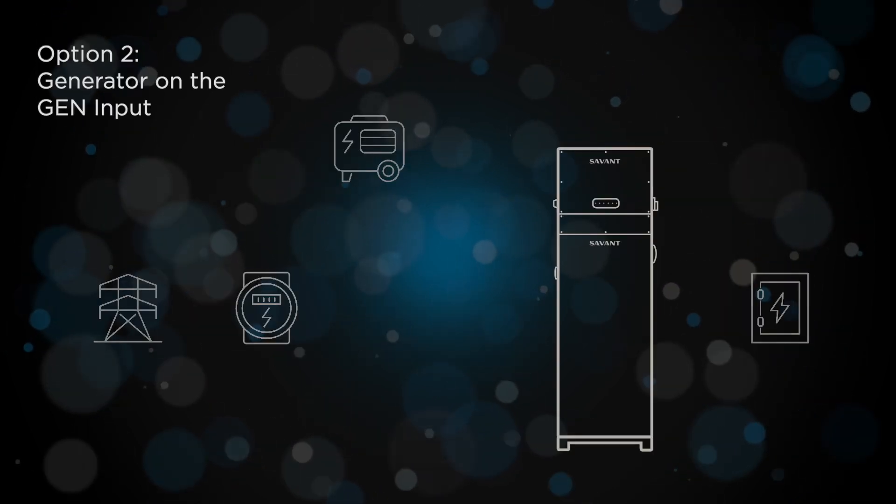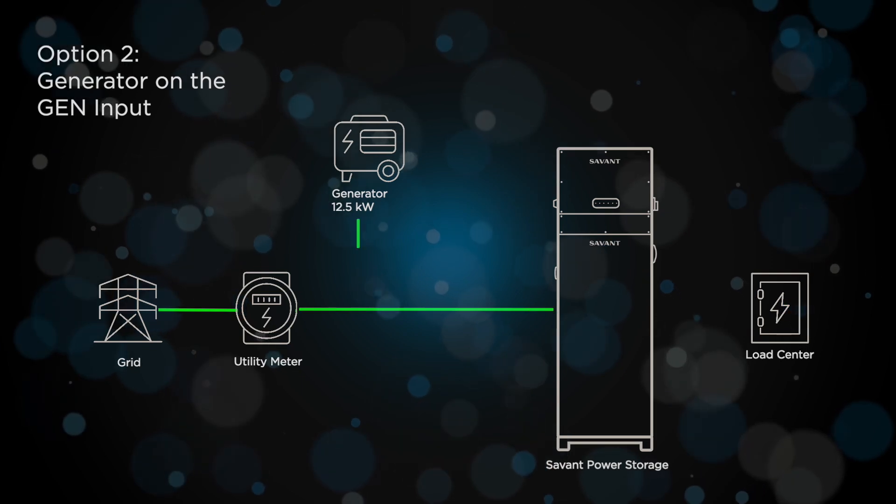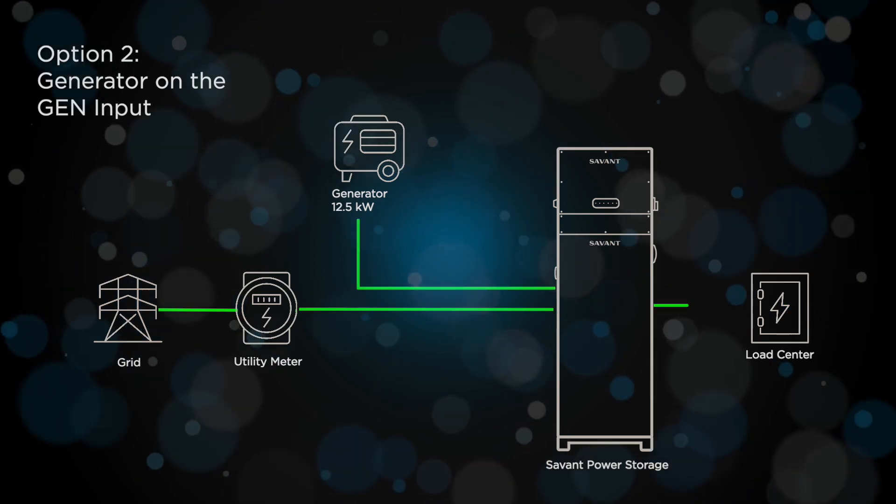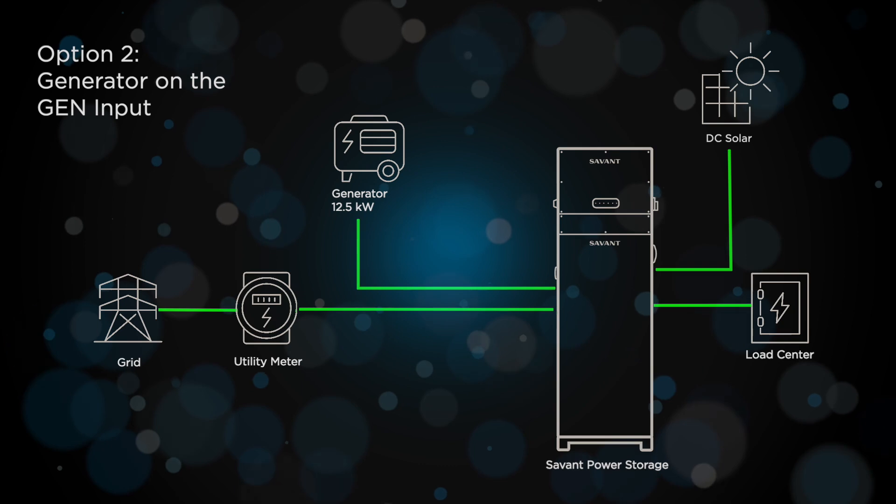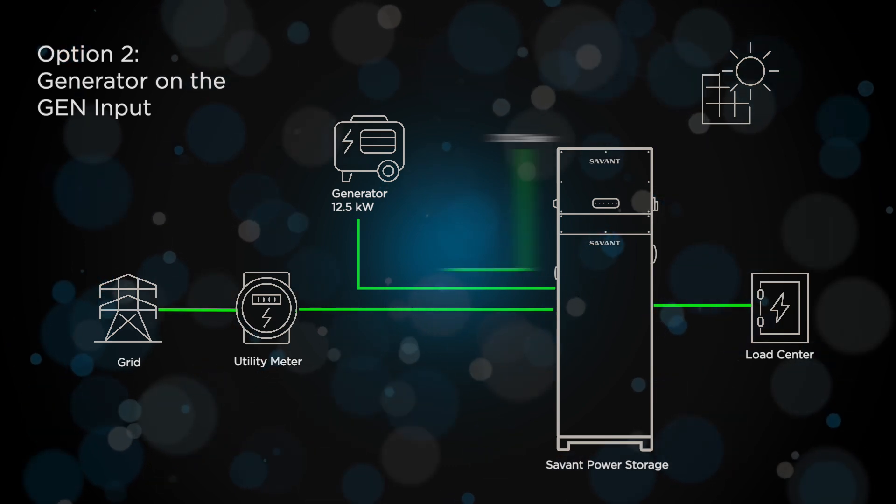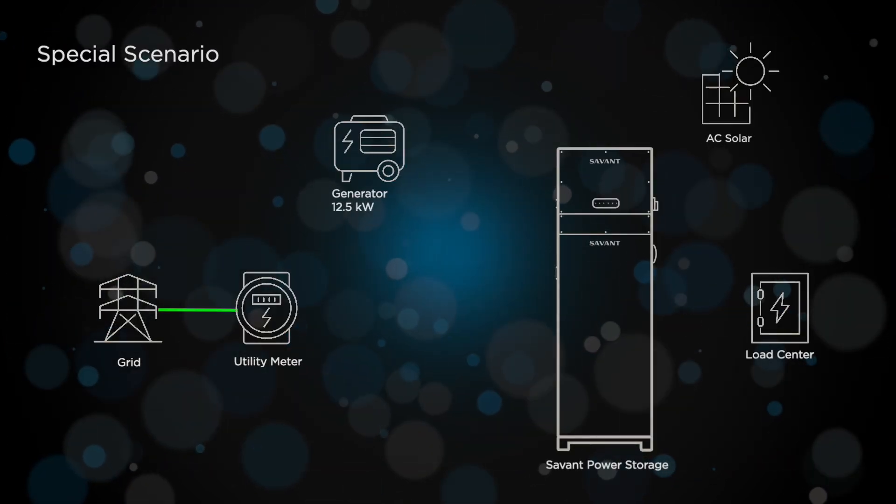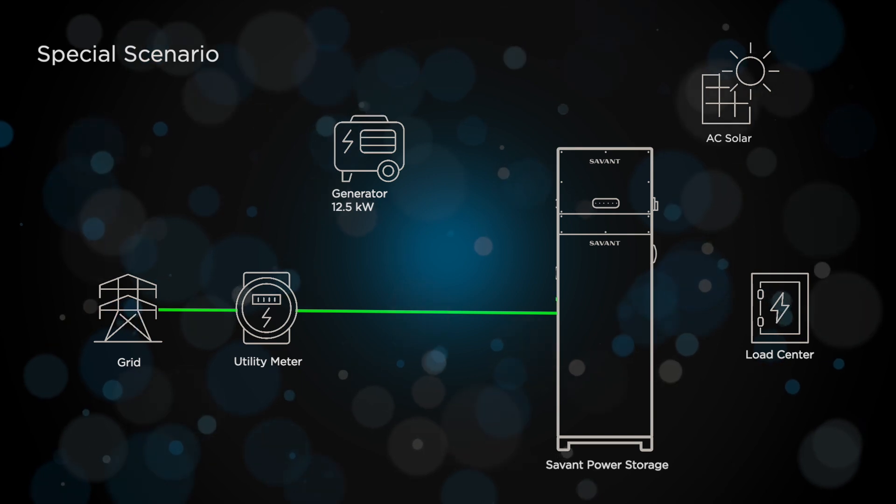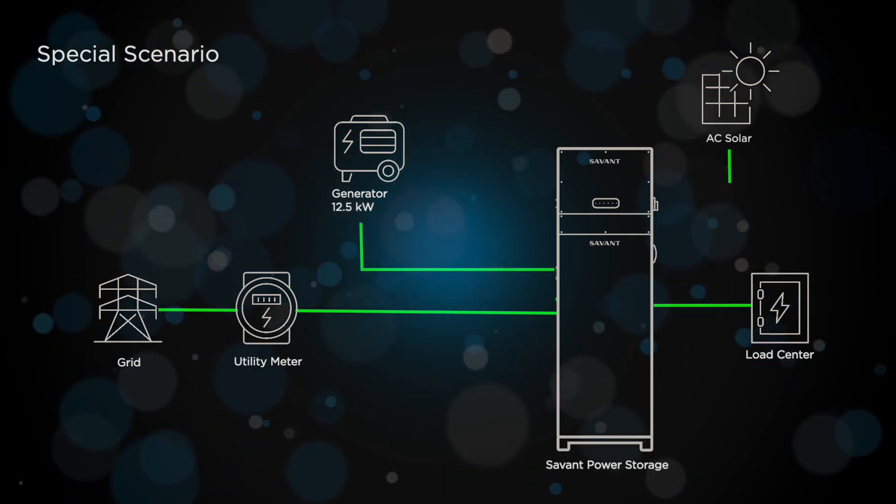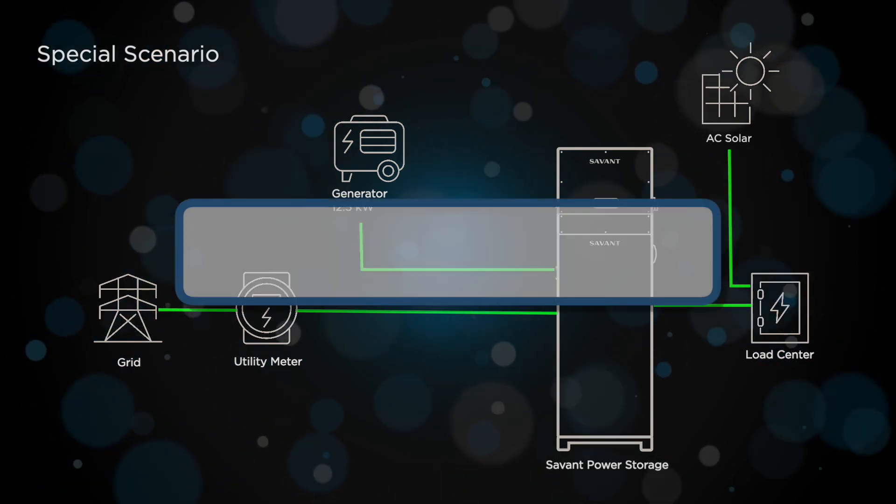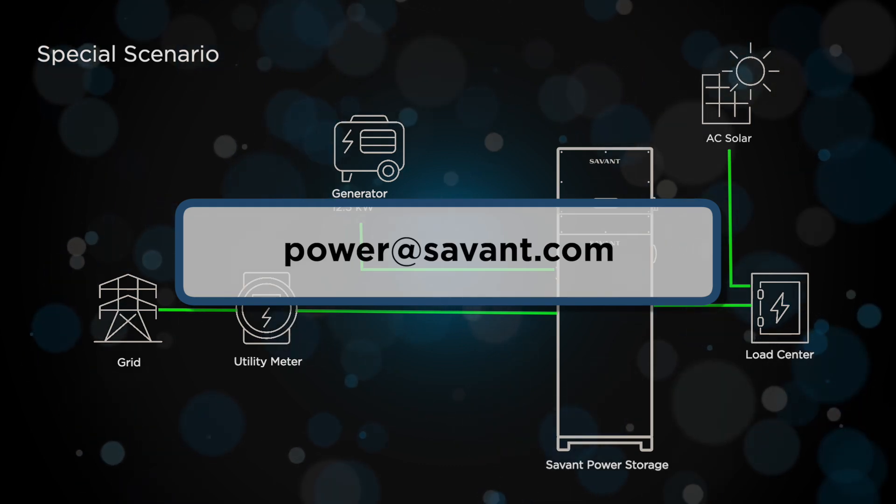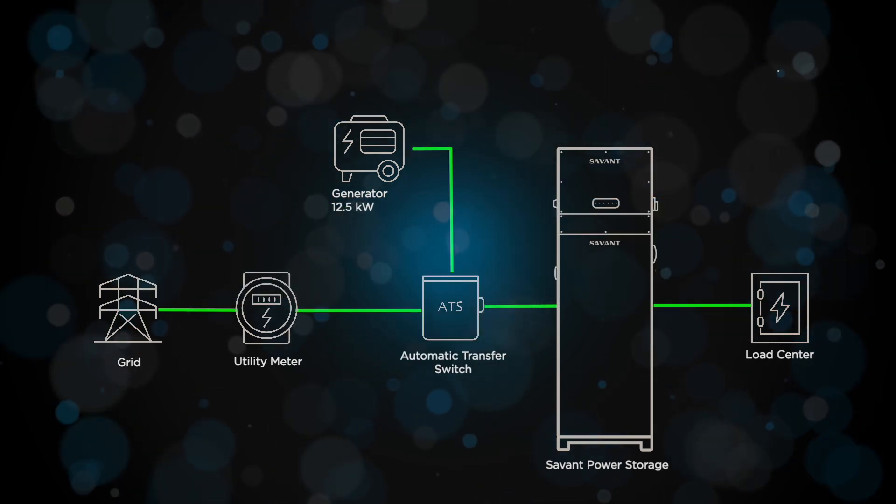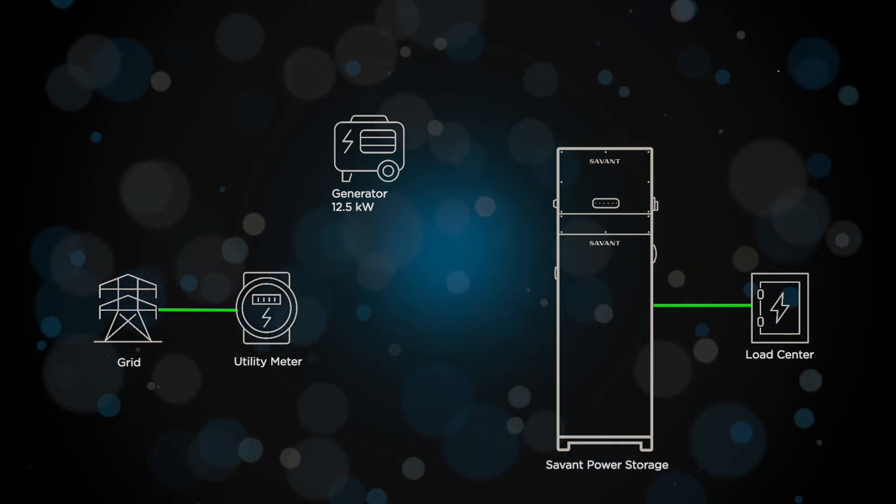Option 2: Connecting to the generator input on the inverter. This allows us to connect DC solar to the PS20. If you have a generator and AC coupled solar, and you cannot connect the AC coupled solar to the generator port like option 1, you need to contact us for special design considerations. Connecting the generator to the generator port eliminates the need for a transfer switch.